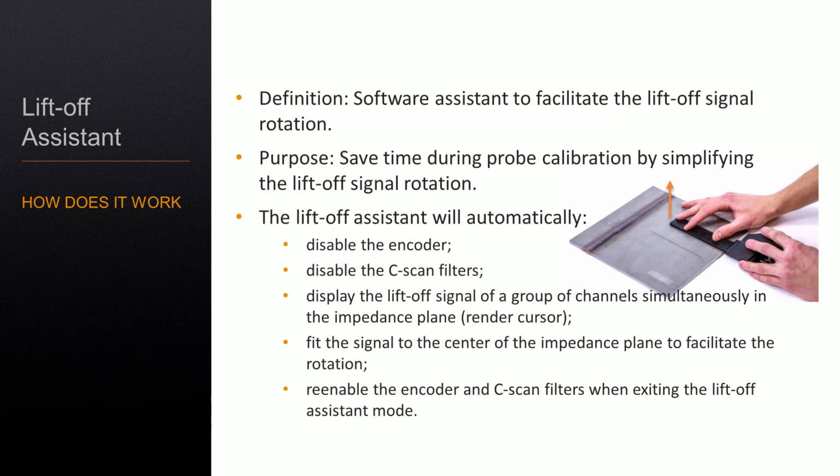So simply to summarize why to use this tool and how it works. Basically, it's a software assistant to facilitate the liftoff signal rotation or any other reference signal we might want to use. It is meant to save time during probe calibration or initial setup by simplifying the signal rotation.